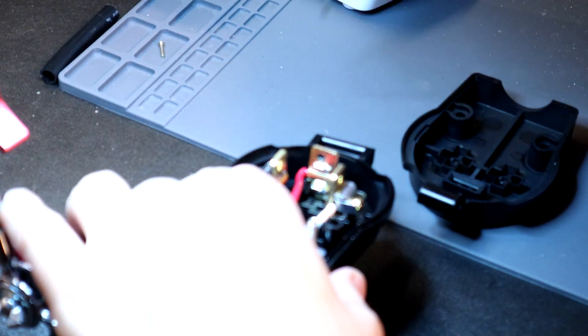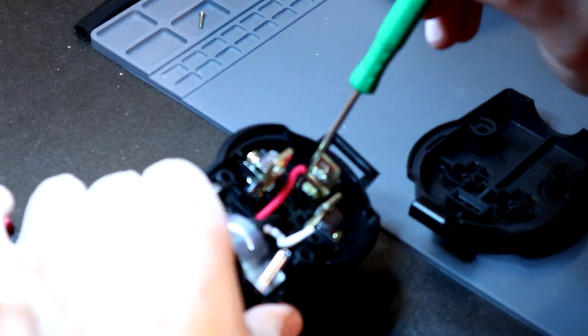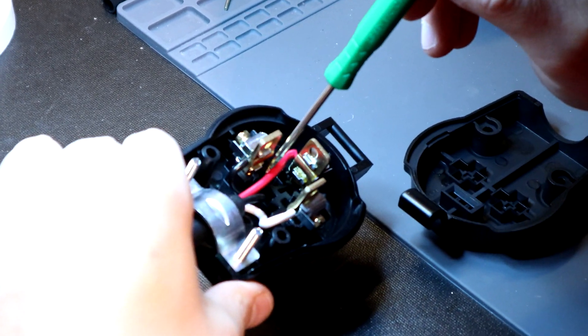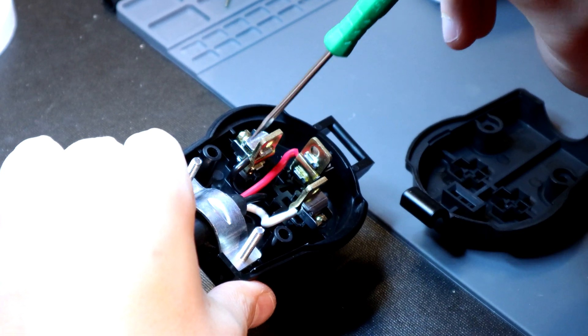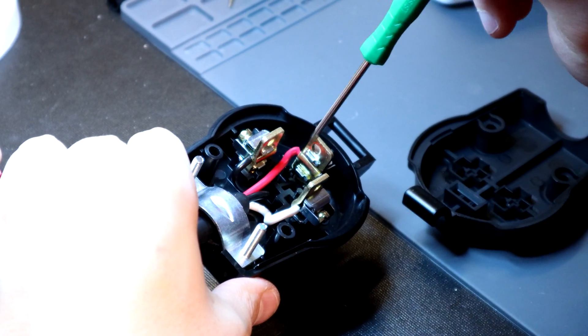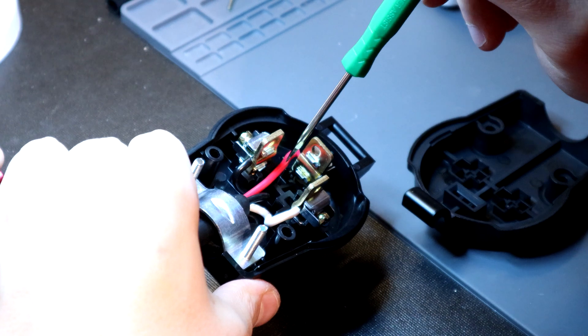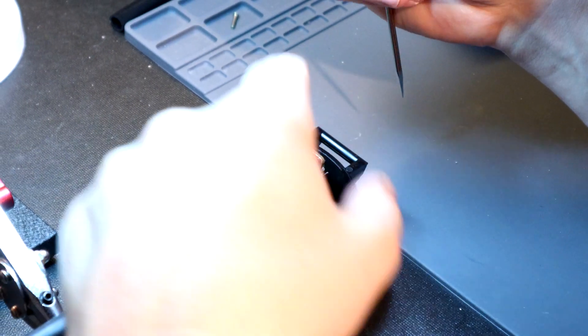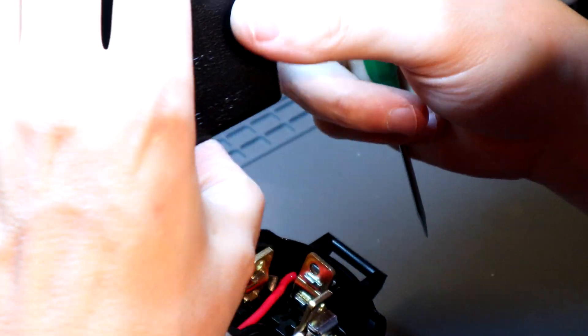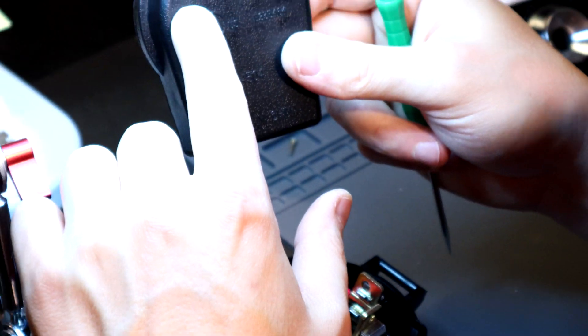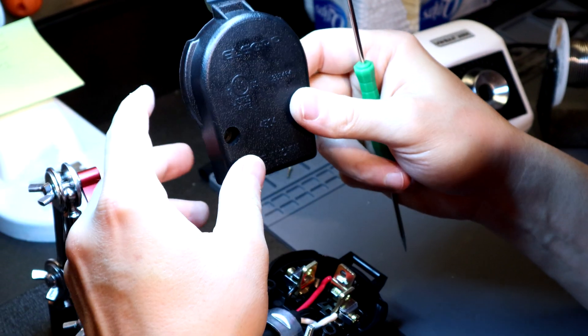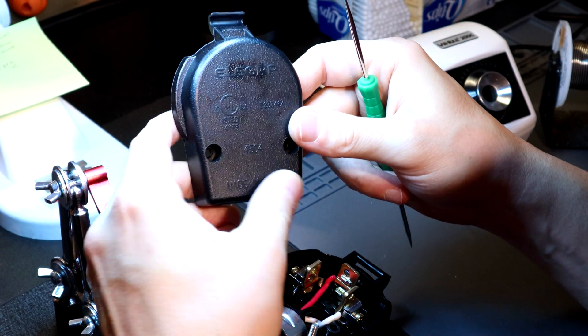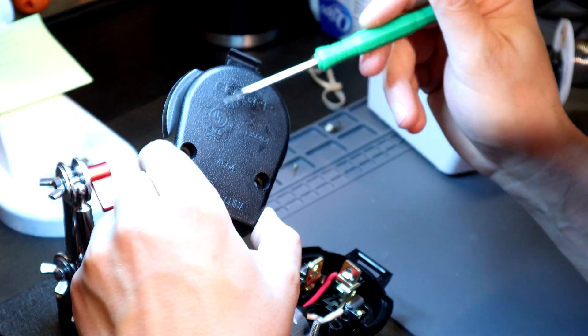A lot of double-shielded cables may not have a ground lead, so what you must do, regardless of what cable you're working with, and regardless of what connector you're working with, you want to go in and make sure that somewhere, either on the cable itself or externally on the housing, you put a note to whoever's working on the cable that red will be ground, and that's totally acceptable to do.